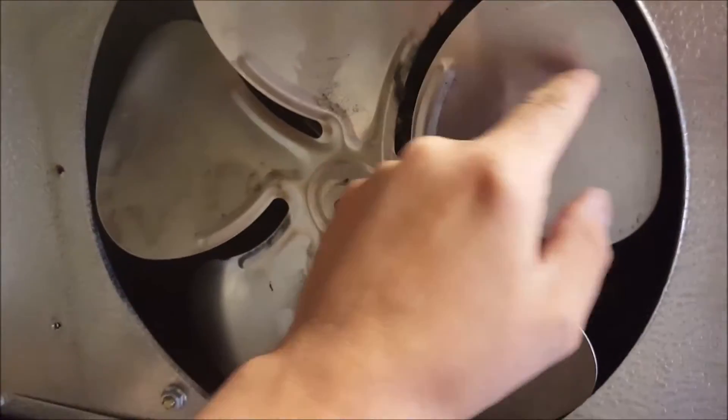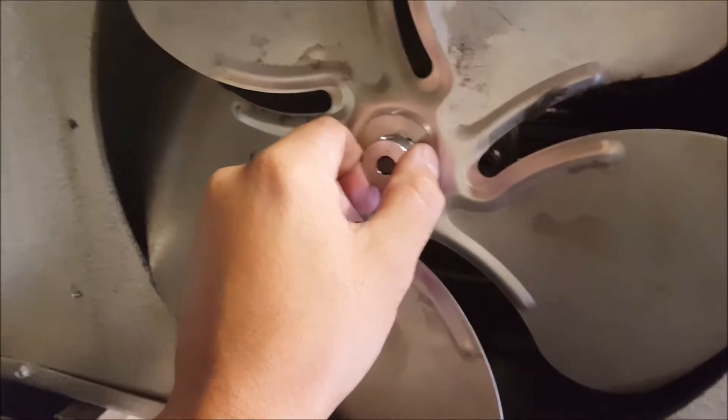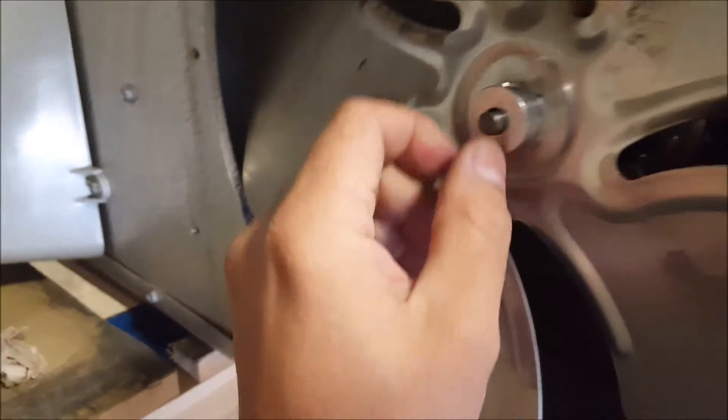When you're replacing these fan blades, you want to check and see, make sure they don't have any hairline cracks. If you have any hairline cracks, then this thing's probably going to break on you at some point. Best to replace it anyway.